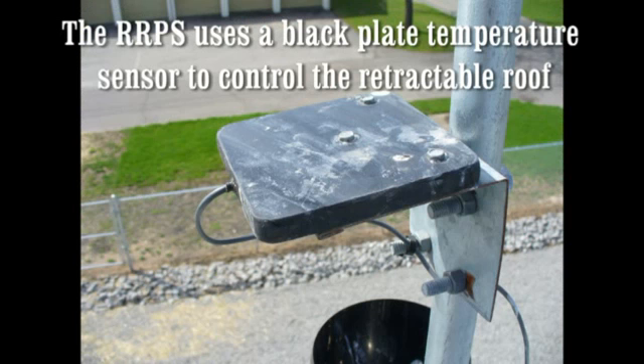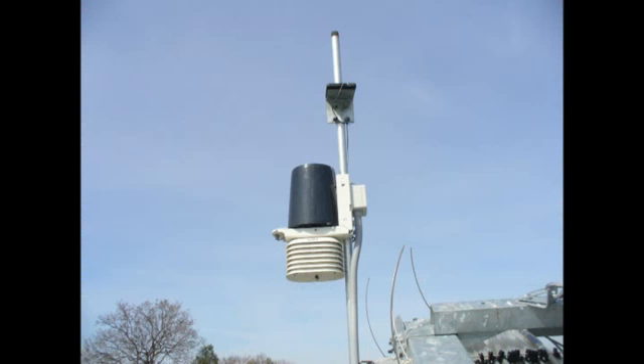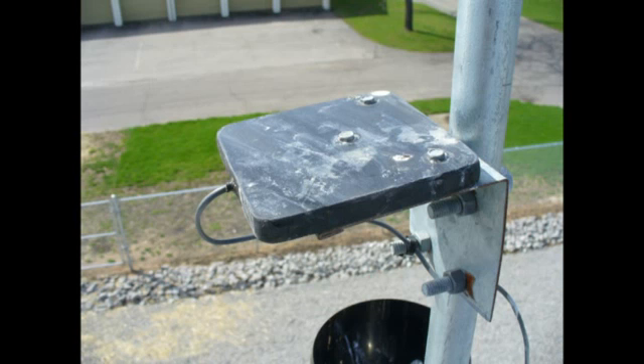Since air temperature is such a poor predictor of plant and soil temperatures when exposed to direct sunlight, the RRPS uses a black plate sensor to provide a more accurate temperature reading to determine when to close and retract the roofs. This sensor is installed on the weather station outside. The black plate temperature changes as changes occur in light levels, air temperature, and wind.